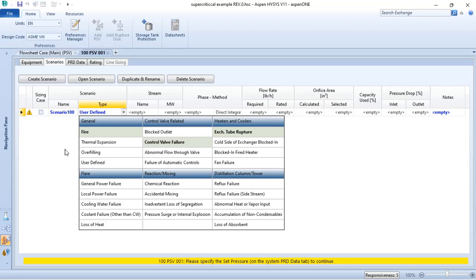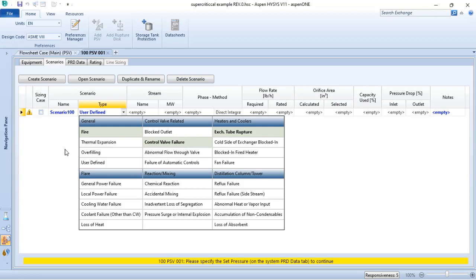So what happens if you have a high pressure upstream of your control valve and it goes to downstream? Most often, the downstream process is not able to reach the same amount of pressure as the upstream of your control valve, and because of that you need to consider pressure relief devices to prevent the rupture of your system.